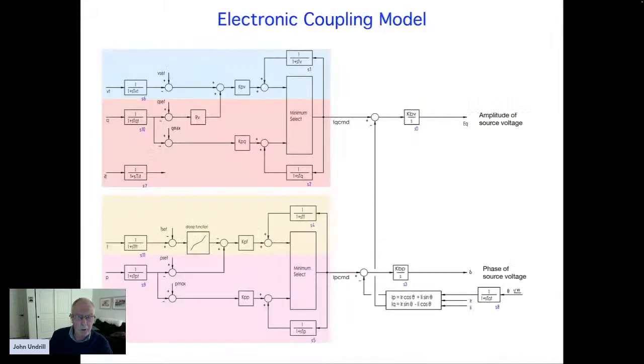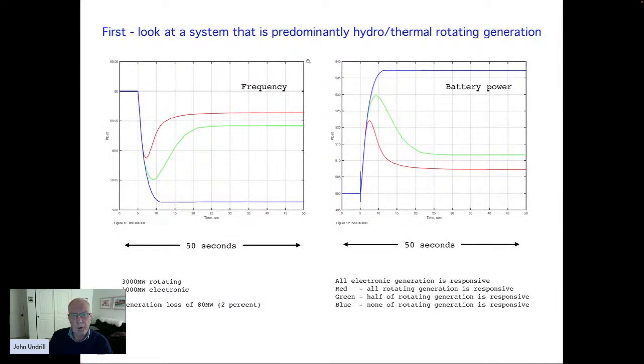Well, let's just look at what we can expect in the next if we had a 100% electronic system. So let's just look at what happens if you have a sudden load increase or a sudden unbalance of load and generation, to call it a sudden load increase, in an all predominantly conventional system, rotating hydro machines, rotating turbine generators. And let's assume that the system's 3/4 rotating and 1/4 electronic. So there's 3,000 megawatts of steam turbine and gas turbine generators, hydro generators, and there's 1,000 megawatts of wind and solar. Suddenly increase the load by 2%.